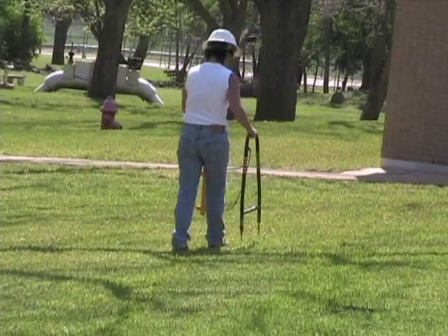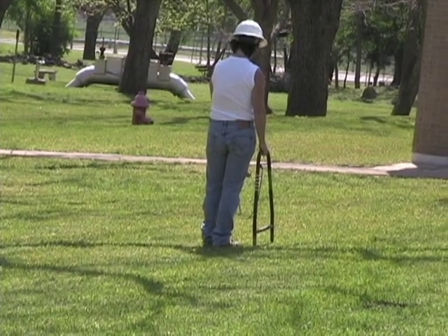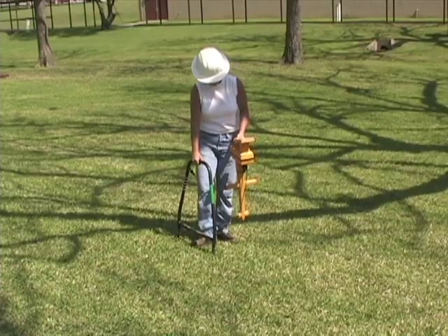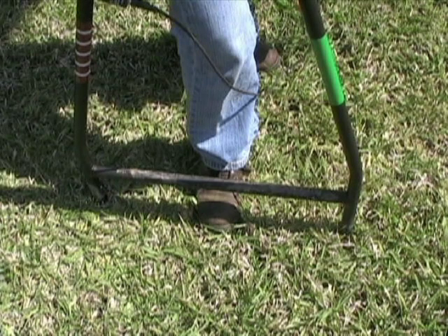Probe the ground back and forth until the fault is centered between the red and green legs of the A-frame. You have now located the fault two-dimensionally. You have centered the A-frame over the fault in the forward and backward position. Now you need to pinpoint the fault in the left-right direction.